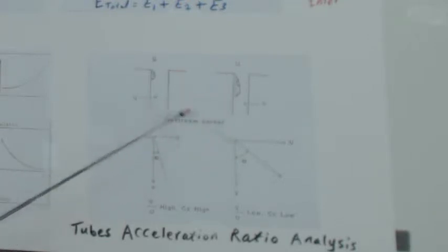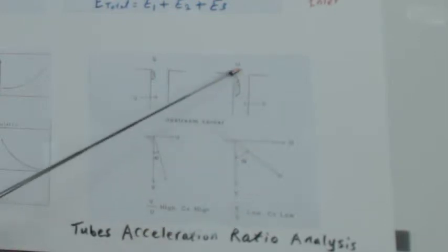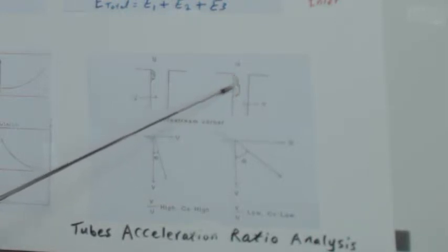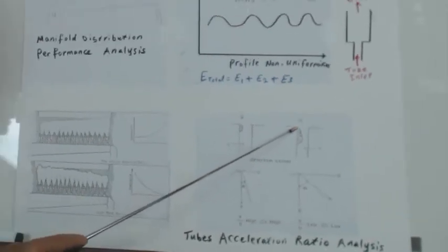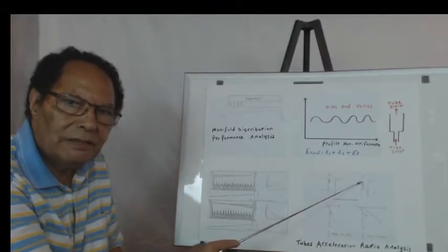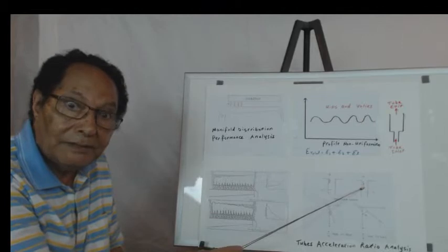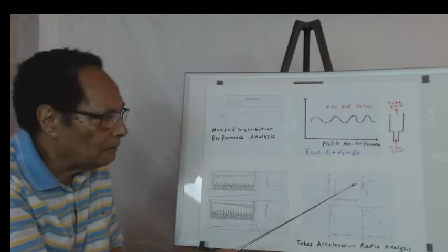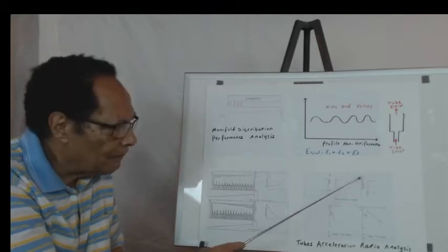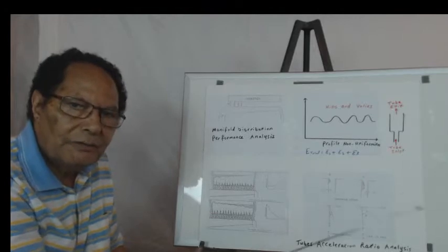Velocity is a vector. I put two vectors here - U is velocity in the manifold and V in the tubes. Here is the angle theta for the vector. In a case like that, you end up with a big eddy. Eddy dissipates energy. Fibers will fluctuate and build up inside these tubes and eventually can be plugged up. It doesn't even have to plug up - just buildup at the inlet of the tubes changes the whole profile.